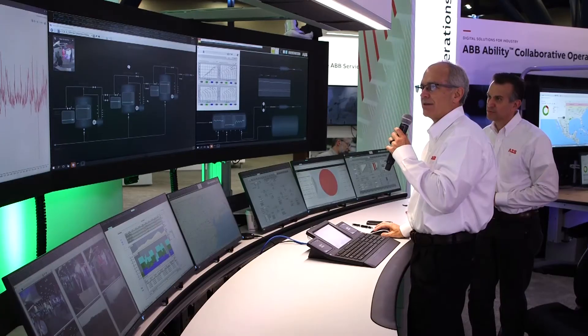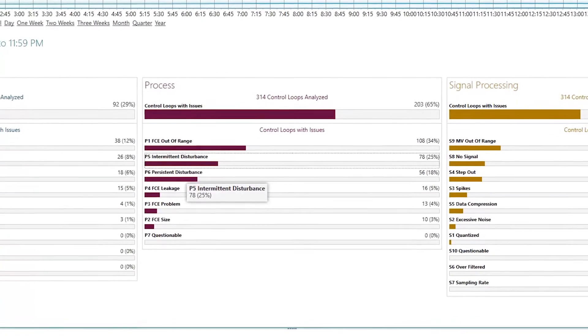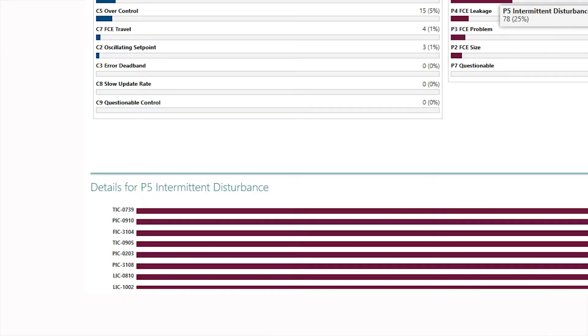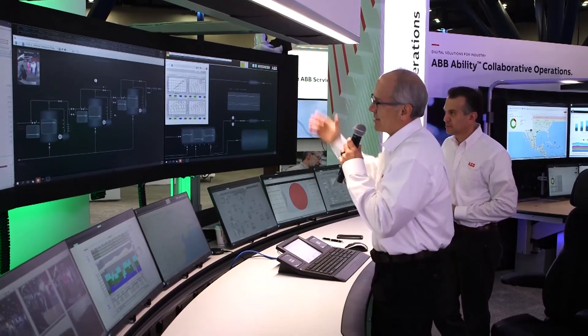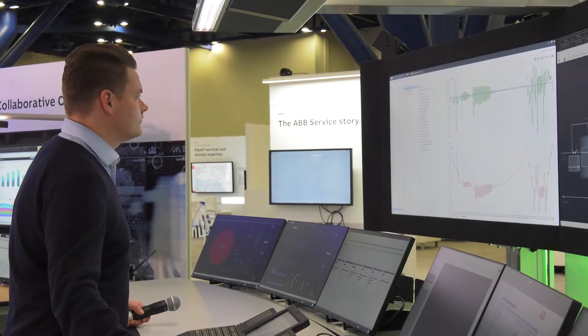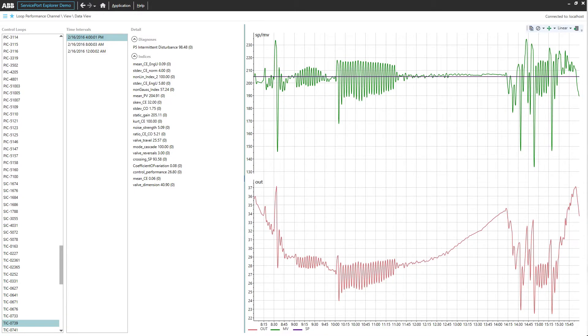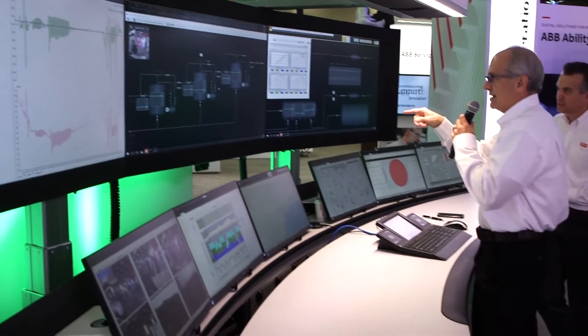Let's do some mining. Let's jump back over here to this loops channel. I'm suspecting you've got an intermittent disturbance — that's what it looks like. So if I go to the event view, go to the process area, and that second KPI called P5 — intermittent disturbance — there's a lot of shaking going on. I can see this TIC-0739. That's in another area of your plant connected through a header to this particular compressor. It's very likely someone might be messing with that loop, causing this problem, and they don't even know they're doing it. Let's click on that KPI and look at the raw data to get that visual value. Look at that — it's oscillating, and this is aligned with that pulse. This is causing your issue. You've already done a visual inspection, so my guess is somebody's just flipped this loop from auto to manual. I can see you have access — could you dig in there and make sure it's in manual, and if it is, flip it back to auto?